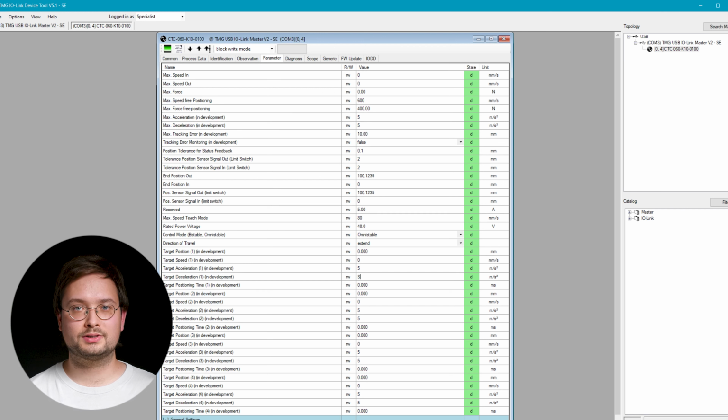If the value 0 is overwritten, the corresponding potentiometer no longer has any effect. The cylinder moves at exactly this value. If we operate the cylinder digitally, the potentiometers are active, or the speed that we specify applies. In modes 3 and 4, this means mode 3 for retracting and mode 4 for extending. For free positioning, we have our own values, and when these are set to 0, then the bit is read out. If you move the cylinder in mode 5 or 6, in free positioning, the above values have no influence because there are separate parameters for the force and the speed.